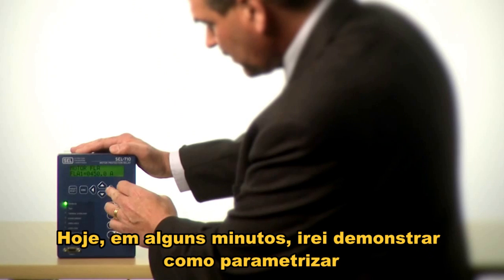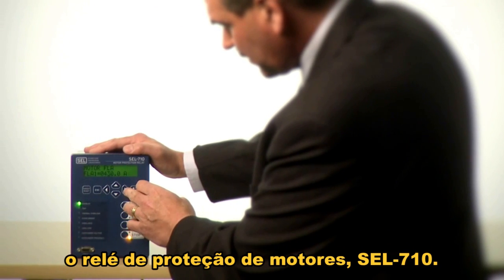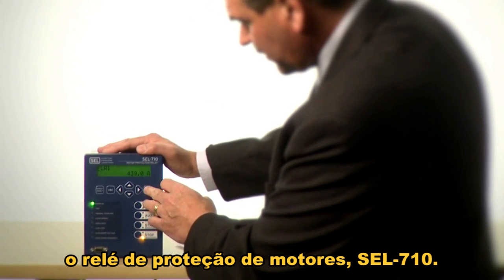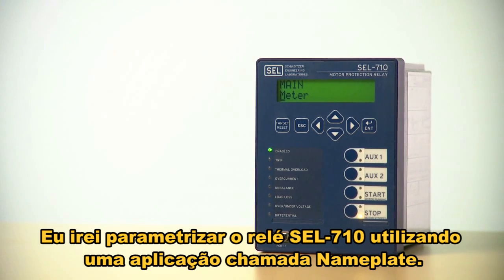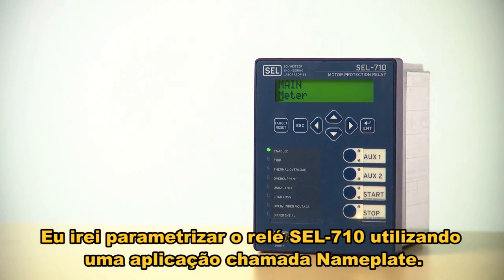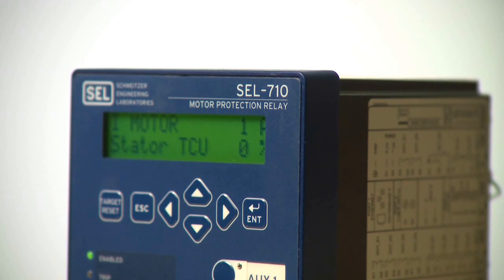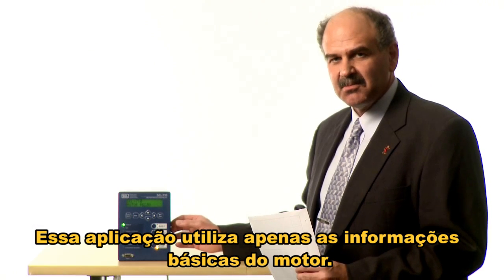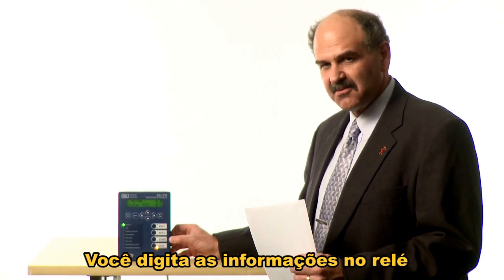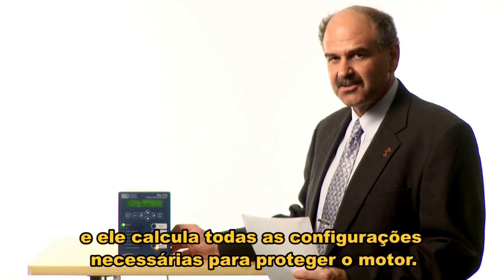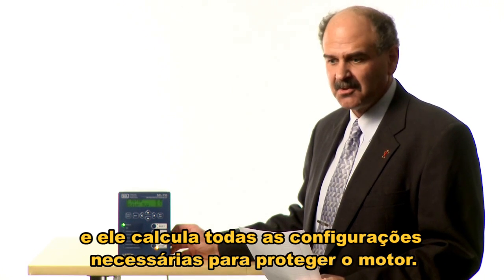I'm going to take a few minutes today and demonstrate how to set up the SEL-710 motor protection relay. I'm going to set the SEL-710 motor protection relay using the nameplate application. This application uses basic motor information. You enter that information into the relay and it calculates all the necessary settings to protect the motor.